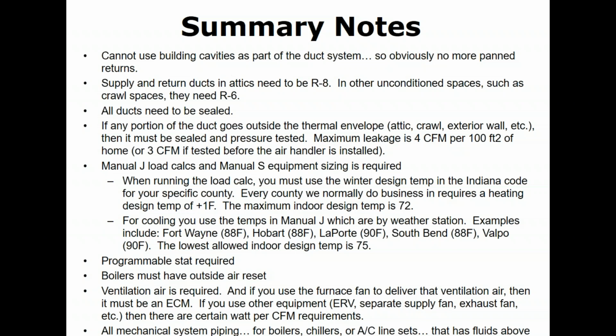Boilers have to have outside air reset. You're going to be required to have ventilation air. If you're bringing that ventilation air through a furnace, it has to be an ECM. If you're bringing it through a fan or an ERV, then that fan or ERV has to have certain watts per CFM requirements met. Mechanical piping systems need to be insulated for both boilers, chillers, and AC line sets if your fluids are warm or cool. So probably the only realistic exception to that would be a radiant floor system. Could be between those two numbers.